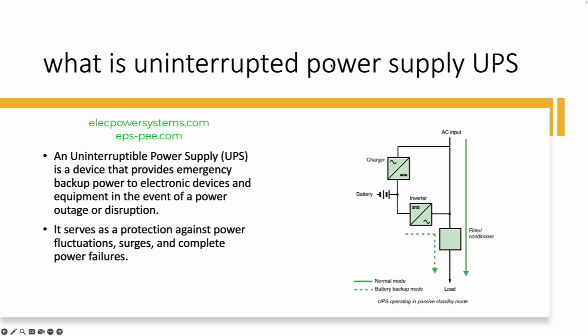An uninterruptible power supply, UPS, is a device that provides emergency backup power to electronic devices and equipment in the event of a power outage or disruption. It serves as a protection against power fluctuations, surges, and complete power failures. The UPS consists of a battery or a bank of batteries that store electrical energy, along with an inverter that converts the stored DC, direct current, power into AC, alternating current, power, which is compatible with most electronic devices.